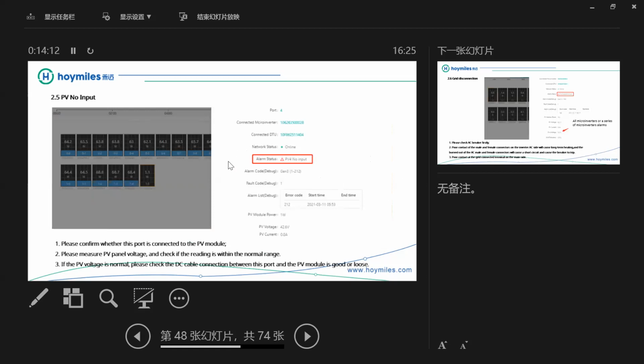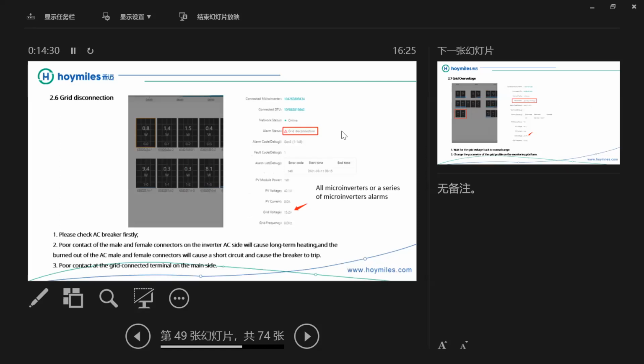And if the alarm shows no input, please confirm whether this port is connected to the PV module, measure the PV panel voltage, and check if the reading is within the normal range. If the PV voltage is normal, please check whether the DC cable connection between this port and the PV module is good or loose. If it shows grid disconnection, please check the AC breaker first. Poor contact of the male and female connectors on the inverter AC side will cause long-term heating, and the burning out of the AC male and female connectors will cause a short circuit and cause the breaker to trip. These factors will all cause this alarm.